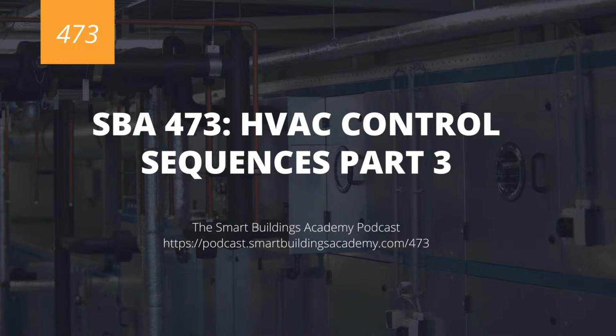Now, these systems tend to serve multiple zones, and how they do that is either by providing constant volume to these zones or spaces, and then varying the discharge air temperature, or by providing a constant discharge air temperature and then varying the airflow, as we saw in the first episode of this series on VAV boxes.